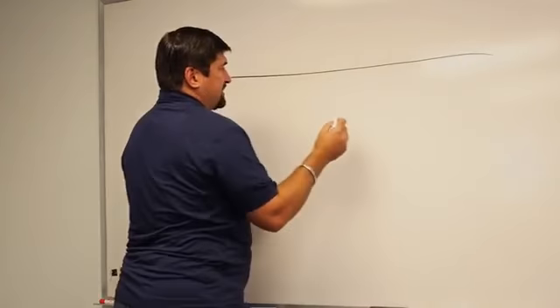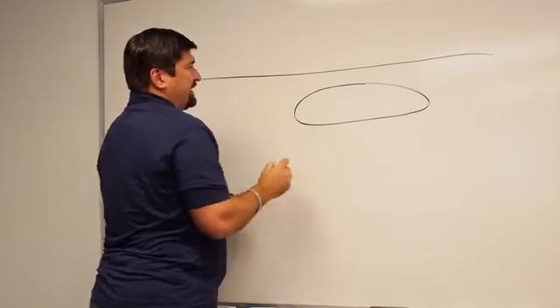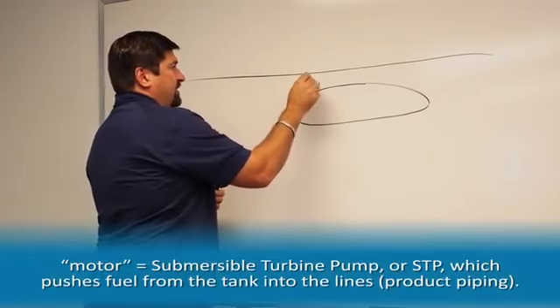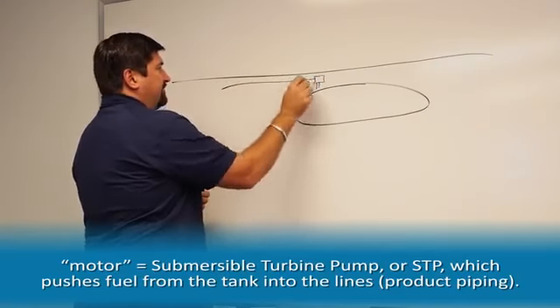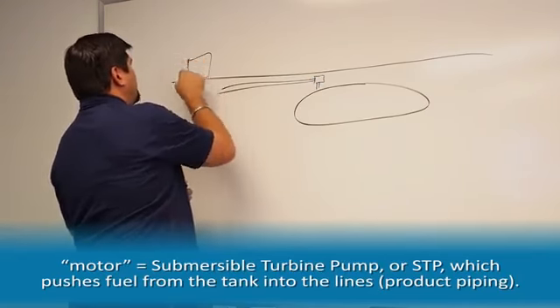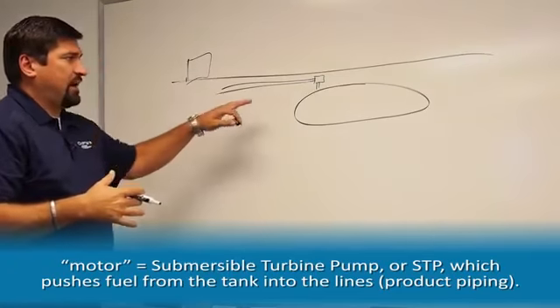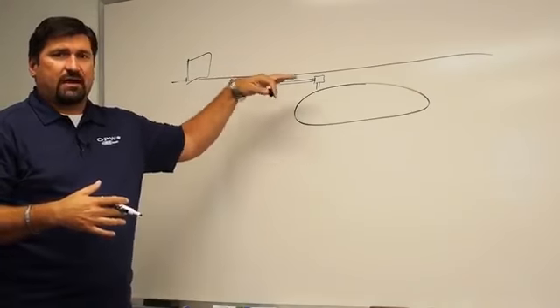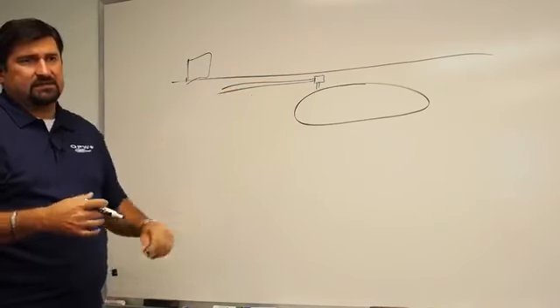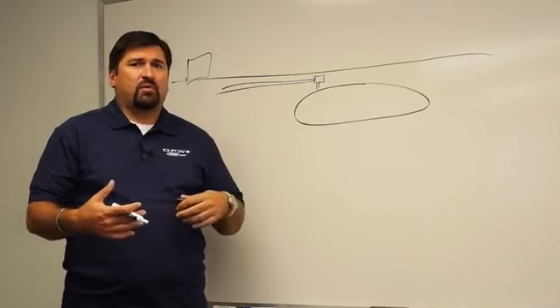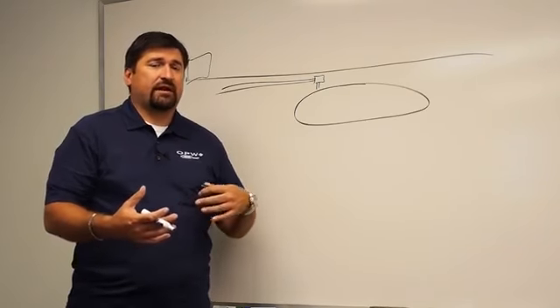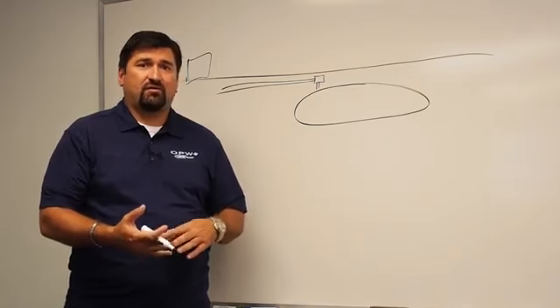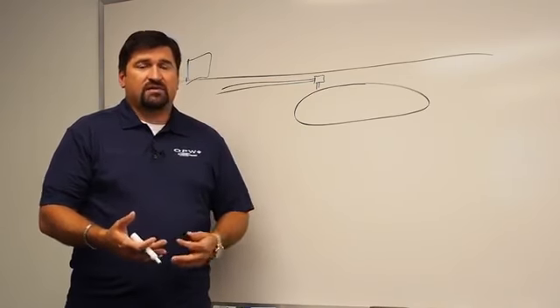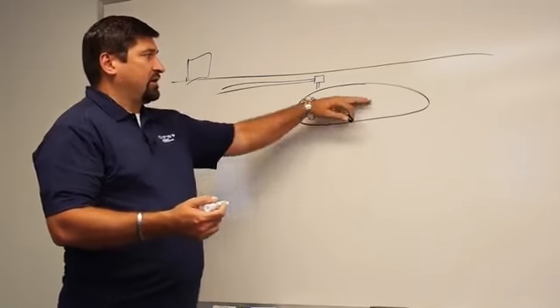Most retail facilities, when you look at what's underground, you have your normal tank, you'll have a motor, and then you'll have product piping coming out to a dispenser. Well, the problem that you have is that all of this is underground. You can't see any of this. So the biggest reason why most people will use an automatic tank gauge is because of regulatory requirements, either federal or state, local municipality regulations, where you're looking at a tank.